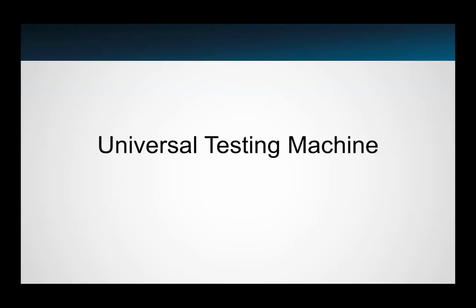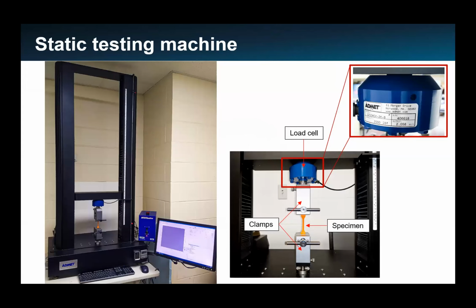Hi, everyone. Today I'll be talking about the universal testing machine and how it works. Simply put, a universal testing machine is a piece of equipment that can apply a controlled force to a material sample, and it can measure the resulting deformation or change in shape or size. By doing that, we can determine how strong a material is and how much it can stretch or bend before breaking. They're typically made up of several key components like a load cell that measures the force being applied, a crosshead that moves up and down to apply the force to the sample, and a set of grips that holds the sample in place.